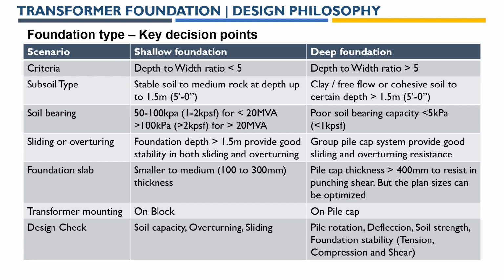Coming to soil bearing comparison: if the soil bearing capacity is 50 to 100 kilopascal, or 1 to 2 kilopound per square feet, we can go for shallow foundation for transformers less than 20 MVA. If the soil bearing is 100 kPa or 2 kilopound per square feet or greater, we can go for shallow foundations even for greater than 20 MVA.